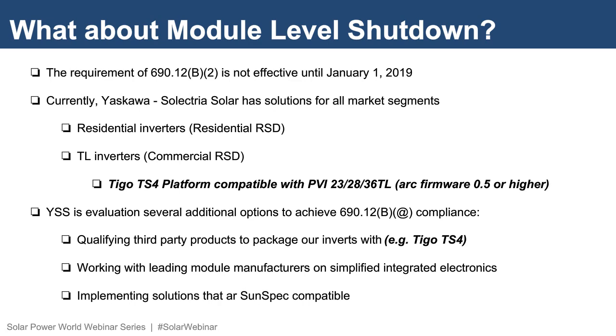Additional to this, we're evaluating several other options in order to achieve compliance with that 690.12(B)(2) article of the 2017 code cycle. This includes qualifying additional third-party products that we can package and recommend our inverters with, similar to the Tigo TS4 platform. We're also working behind the scenes with the leading module manufacturers on simplified integrated electronics. So, switches, devices internal to the modules at the module junction box, make a lot of sense for module level shutdown. And we're working to follow the industry trends and harmonize with the other work going on within the industry.